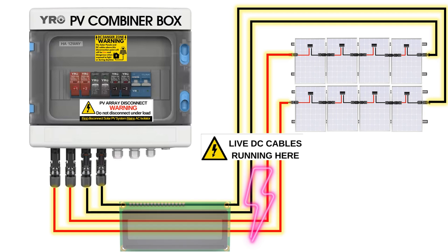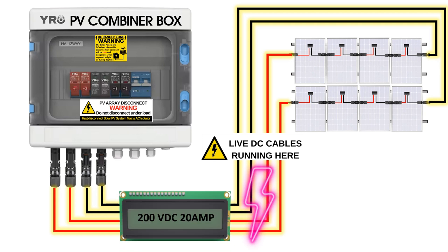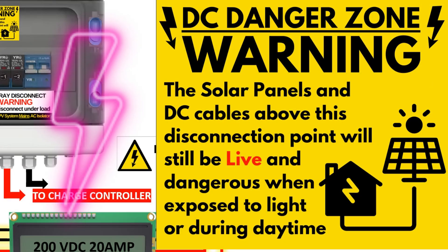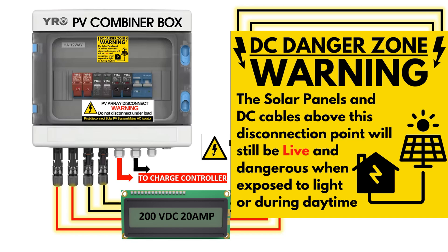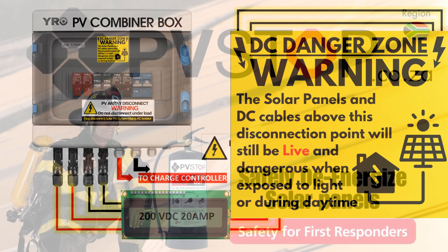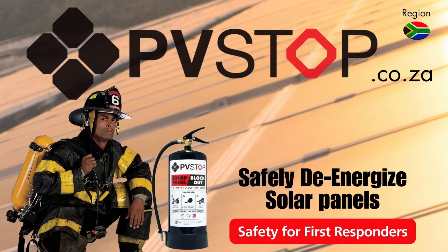Your 200-volt, 20-amp system at the PV combiner box will go to your charge controller. This is a critical DC zone warning: the solar panels and DC cables above this connection point will be live and dangerous when exposed to light or daylight. Even under overcast or artificial light they will still produce power. By disconnecting your PV combiner box, there are still many wires that remain live — you need to take note of that.